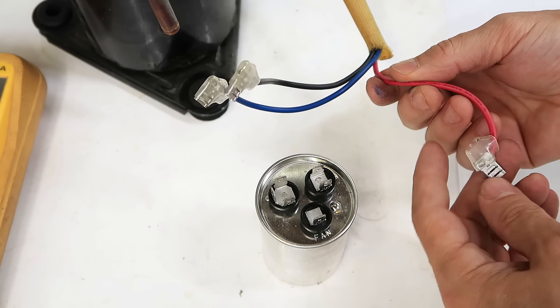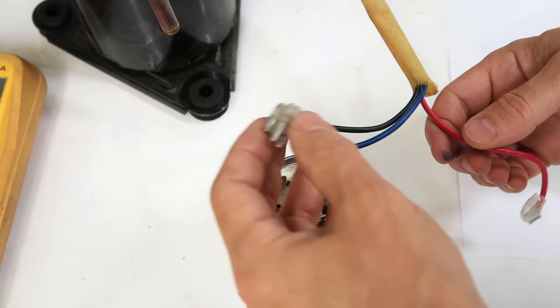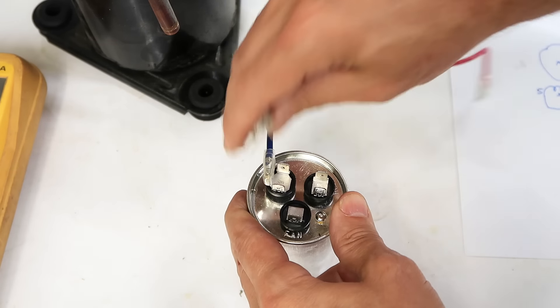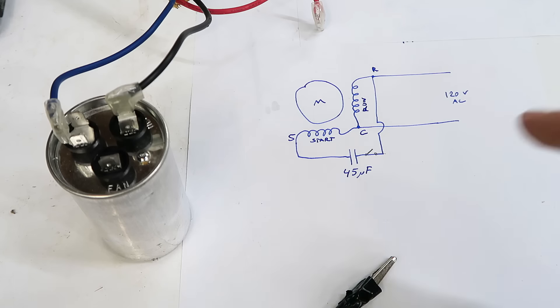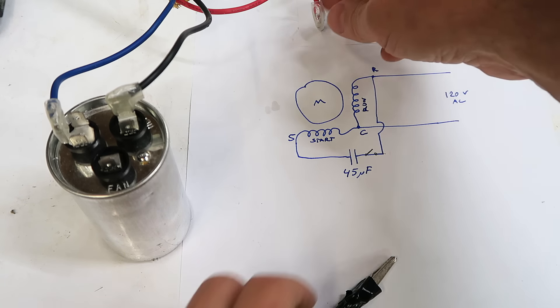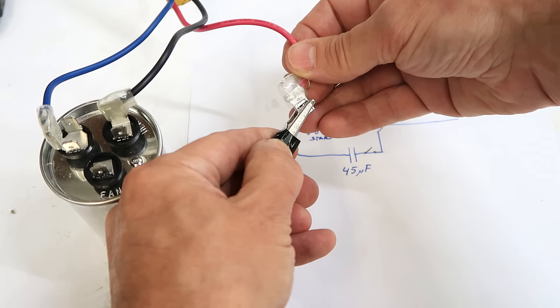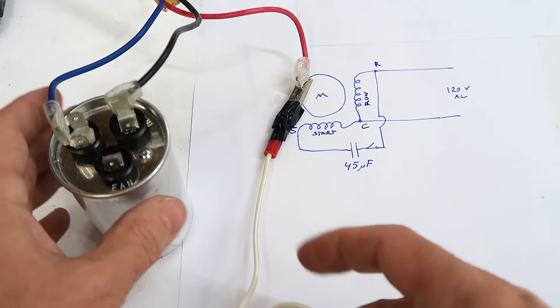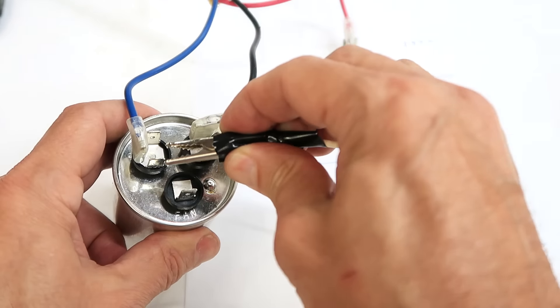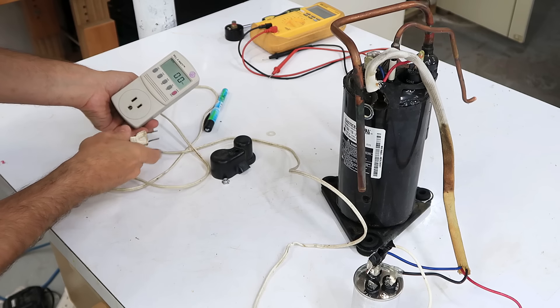With the red wire going to common, I know the other two connect to the capacitor and that's not the fan one, so it goes to this one and this one. The 120 volt power goes to common and the run winding. Common is the red terminal here, and the blue lead here goes to R. I'll just try it on here. Let's plug that in and see what happens.